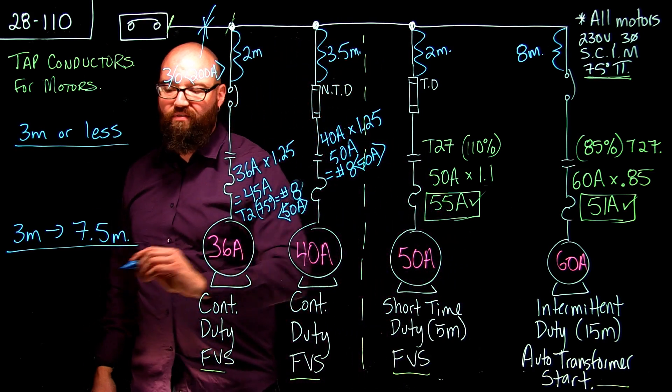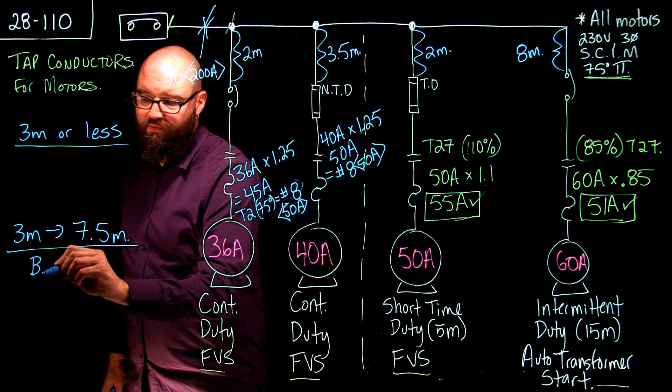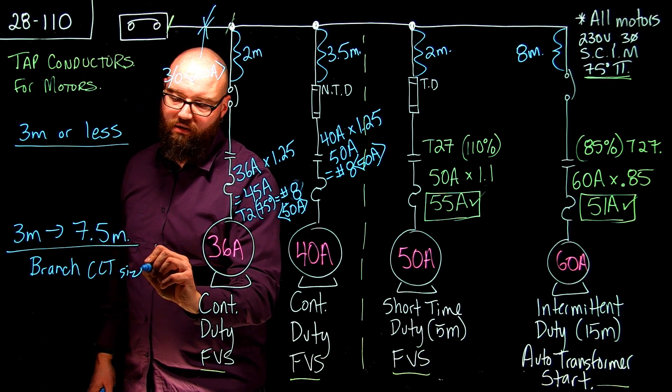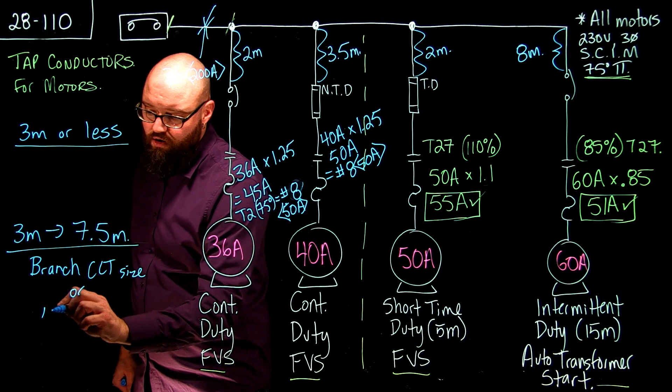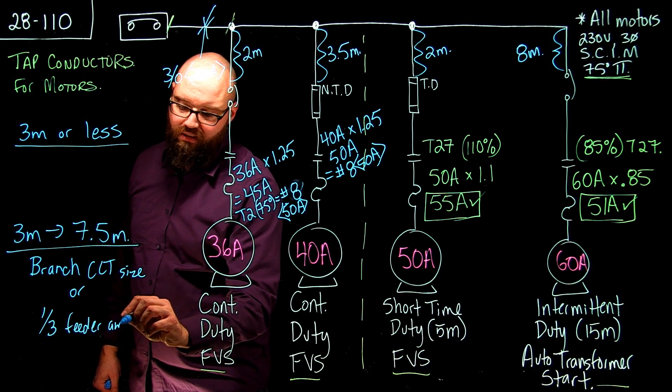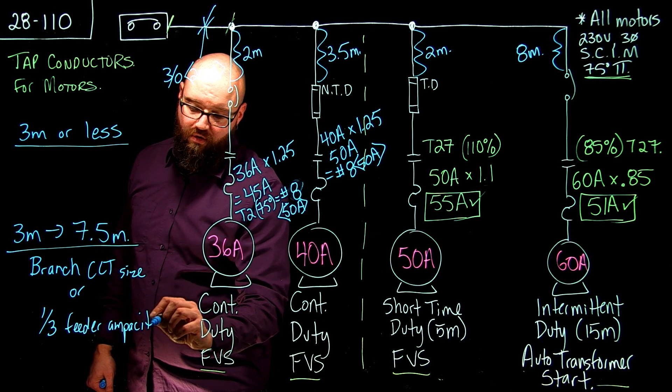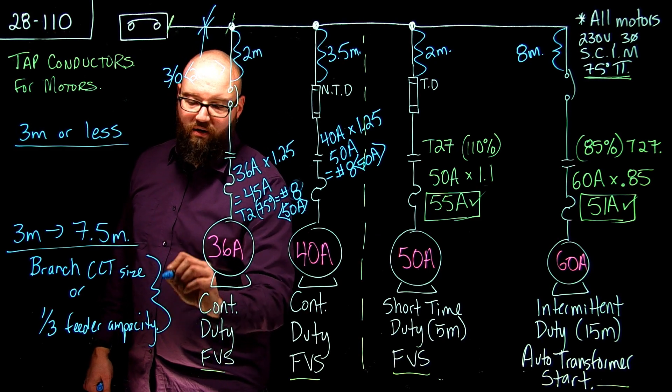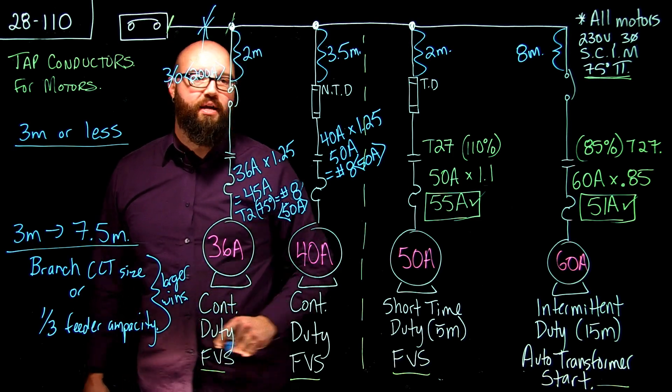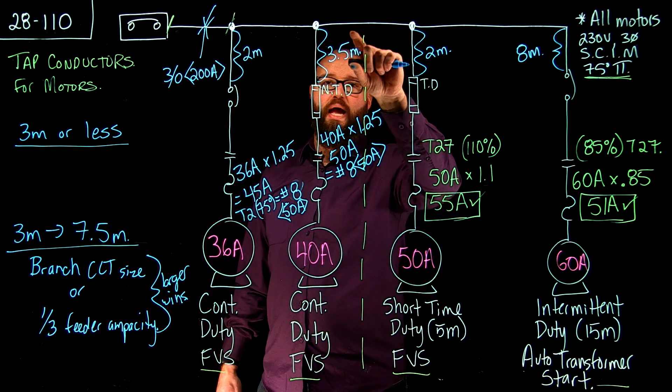We are between 3 meters and 7.5 meters and there's something special we got to do there. When we're between 3 meters and 7.5 meters we're going to go either the branch circuit size or one-third the feeder ampacity.